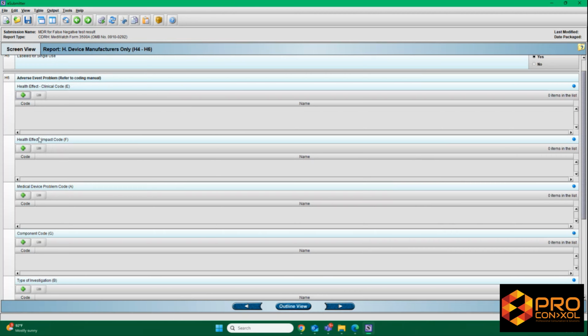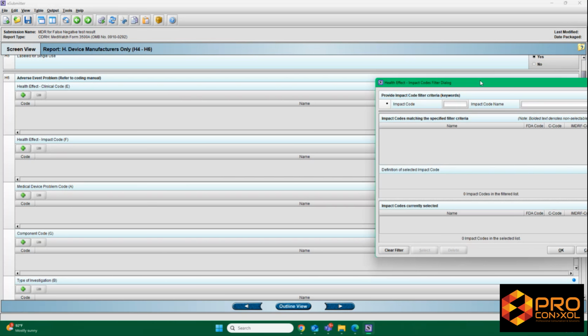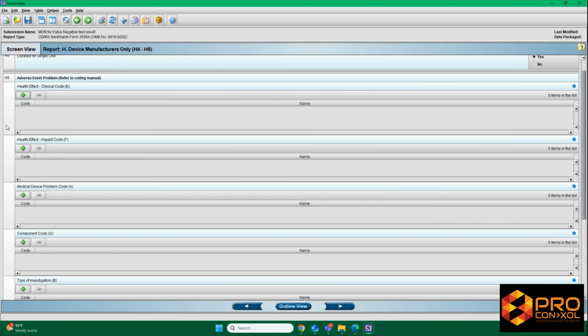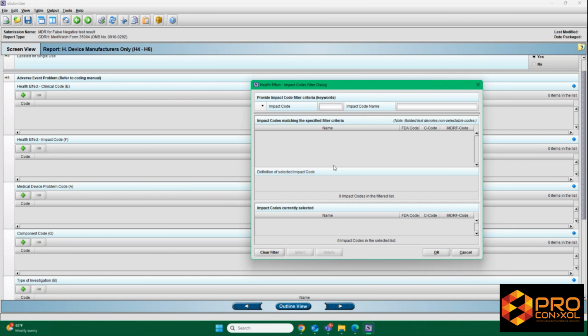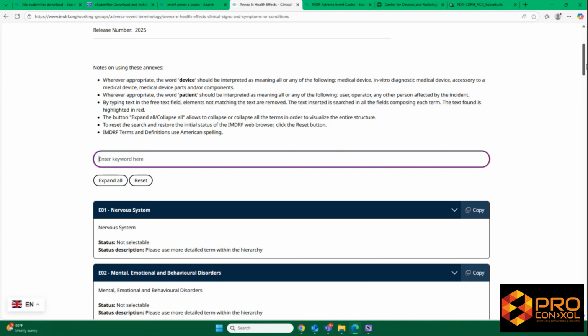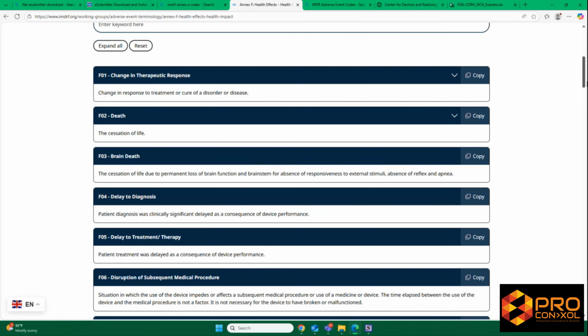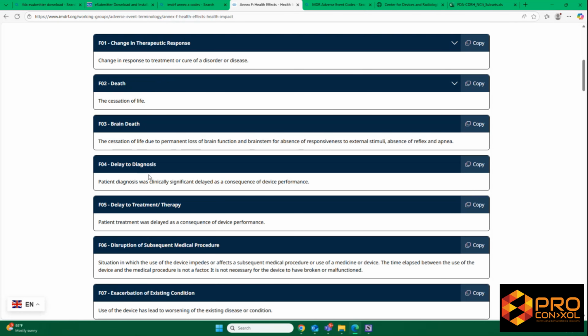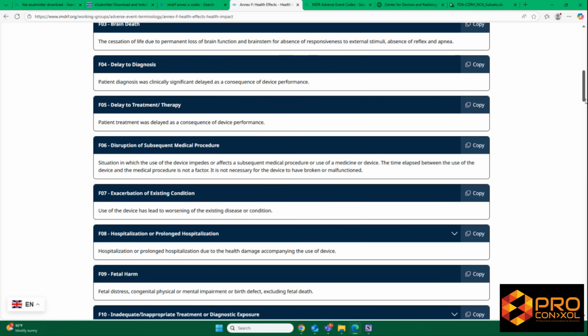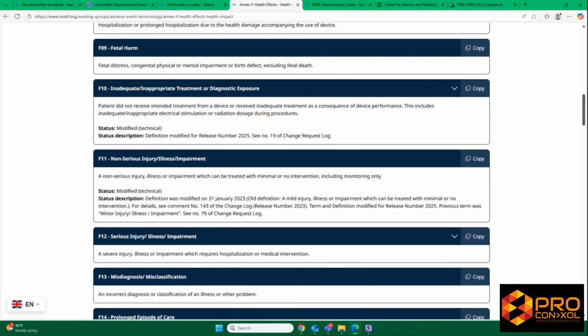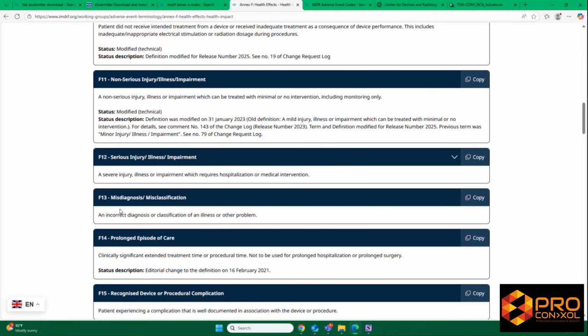For this exercise, I'm going to intentionally skip the clinical code E, and towards the end of the video I'll explain why. Now I'm going to start with the impact code F. First, we will go to the IMDRF website and look for that Annex F. Here we will read carefully and explore all the different codes and their subcodes to find out the exact code that applies to our complaints or device issues that we have in our hand.